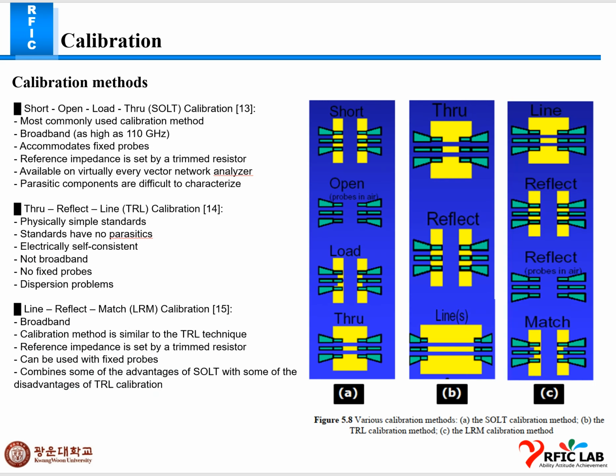Now this part is about calibration methods. What methods have been used? Various calibration methods are used, like the short-open-load calibration method, TRL and LRM calibration methods. Simultaneously, look at the picture also for better understanding, starting with figure 5.8.